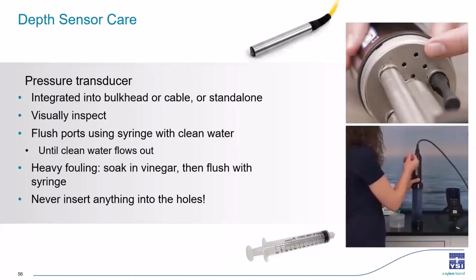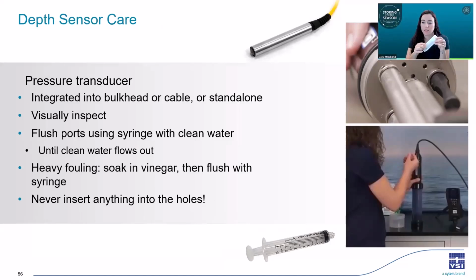And last, we have the depth sensor. You might have one integrated into your instrument body or into the cable assembly, or this can also apply for a standalone pressure transducer as well. You just want to clean off any debris. If you have an internal depth sensor specifically, you want to look into the depth ports. If you see anything blocking them, flush them out with a syringe. We include one with every instrument that has an internal depth sensor. And then just keep flushing with a syringe and clean water until the water comes out clear.